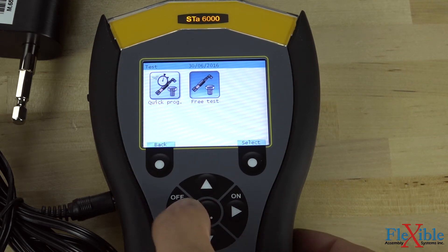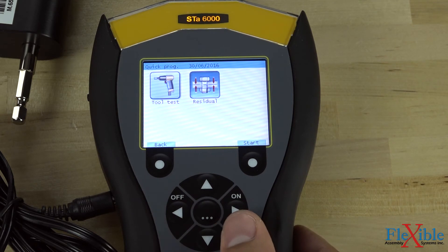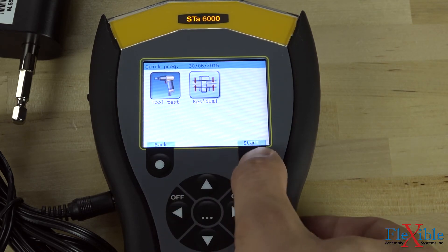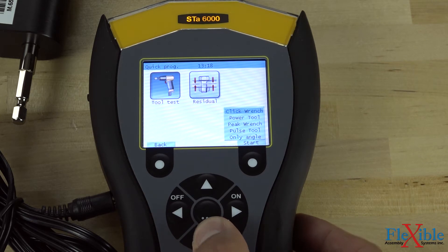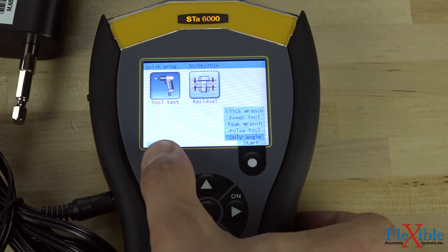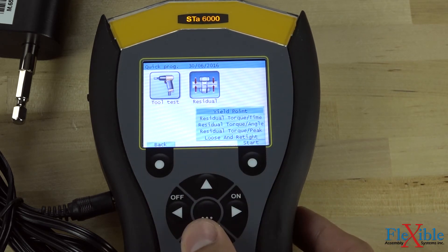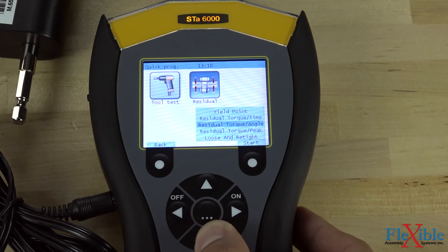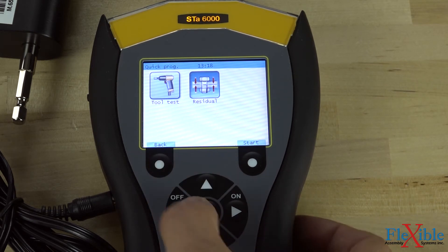If we back out again, we can select quick program. Inside this menu, we have the option to select tool test or residual. Let's select tool test. We must now select the test from either click wrench, power tool, peak wrench, pulse tool, or only angle. If you wanted to test your joint instead, you would select residual and then select from the list displayed. For this video, we will set up a power tool test.